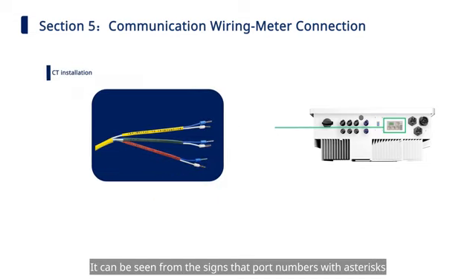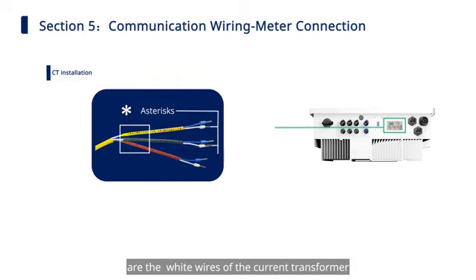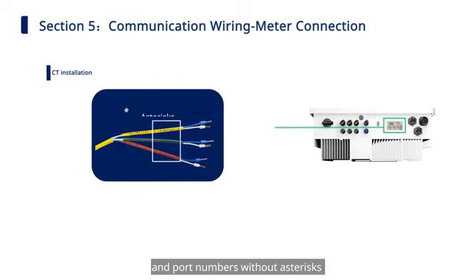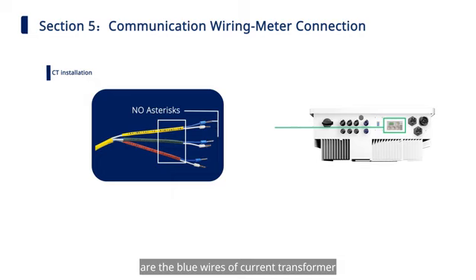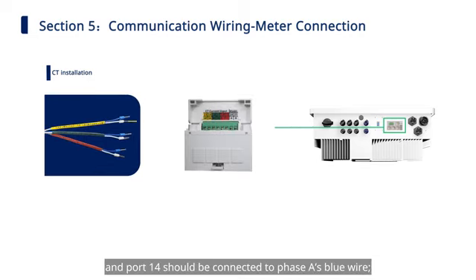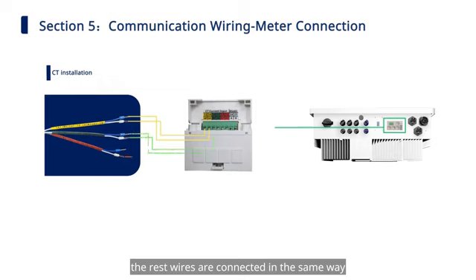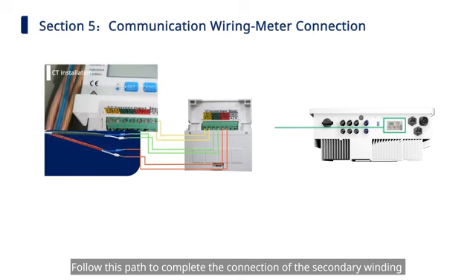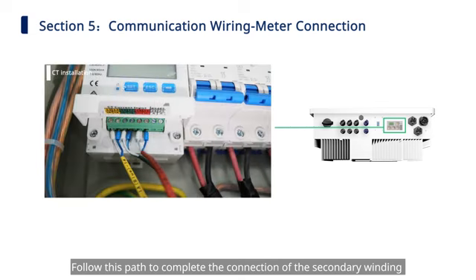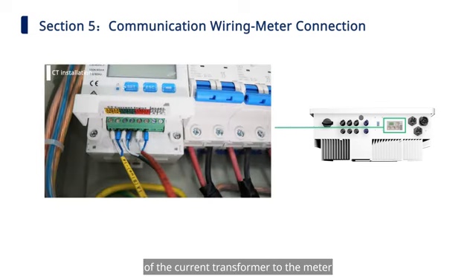It can be seen from the signs that port numbers with asterisks are the white wires of current transformer, and port numbers without asterisks are the blue wires of the current transformer. Therefore, port 13 should be connected to phase A's white wire, and port 14 should be connected to phase A's blue wire. The rest wires are connected in the same way. Follow this path to complete the connection of the secondary winding of the current transformer to the meter.